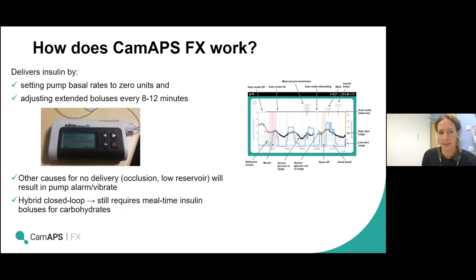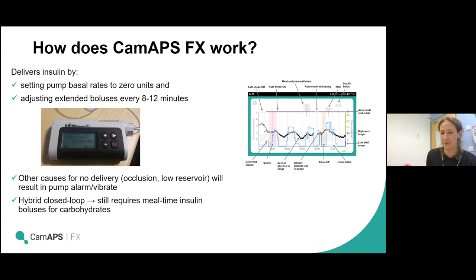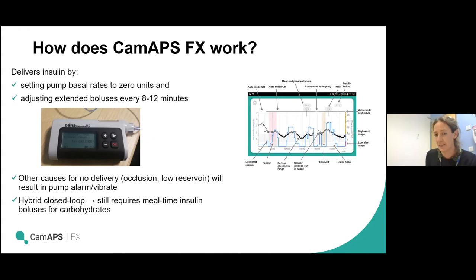In terms of how the system works: with standard insulin pumps there's a constant basal rate and boluses for meals. The closed loop system sets the pump's own basal rates to zero and then calculates new rates every 10 to 12 minutes, allowing it to respond to glucose levels very flexibly. You can see this on the graph — the dots are the continuous glucose monitoring levels and the light blue line is insulin delivery, going up and down in response to glucose, a bit like a New York skyline.